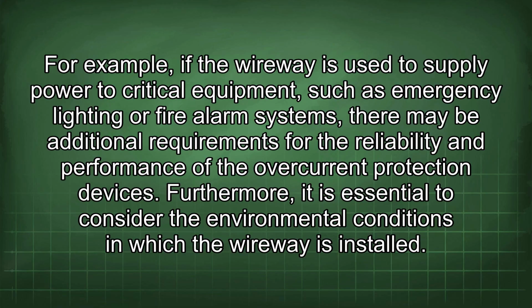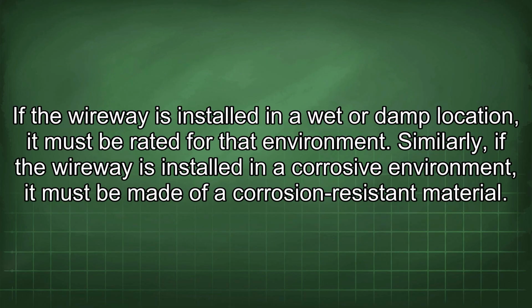Furthermore, it is essential to consider the environmental conditions in which the wireway is installed. If the wireway is installed in a wet or damp location, it must be rated for that environment. Similarly, if the wireway is installed in a corrosive environment, it must be made of a corrosion-resistant material.